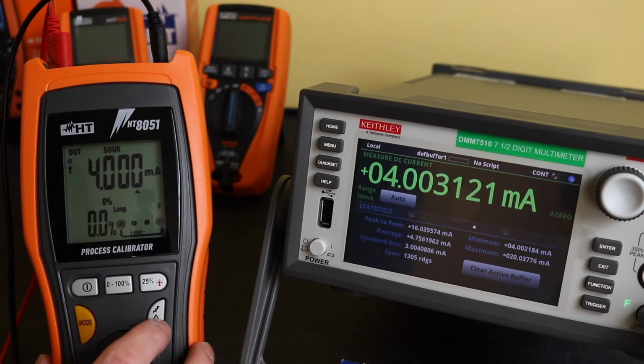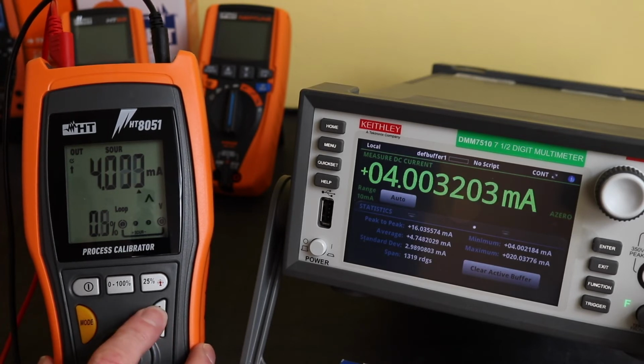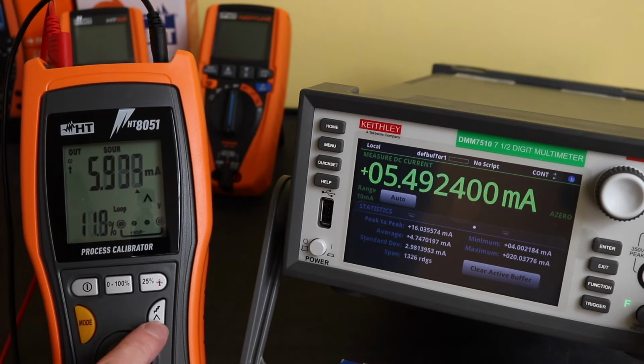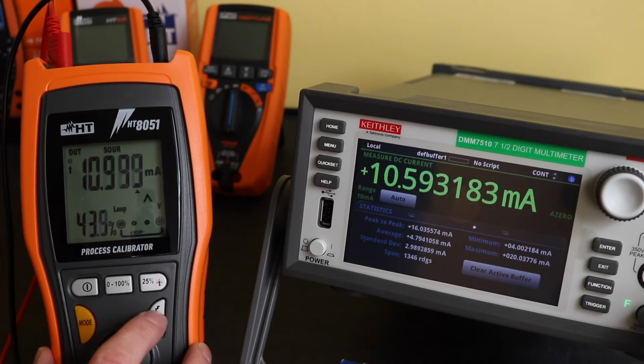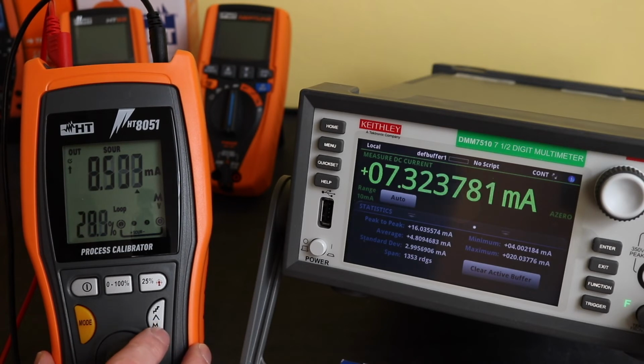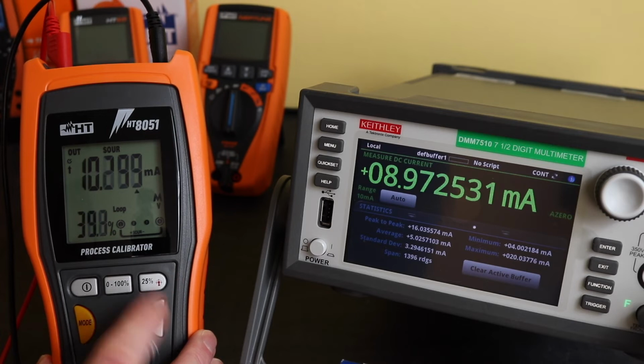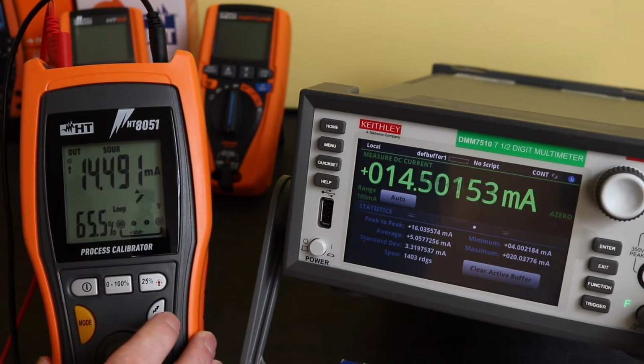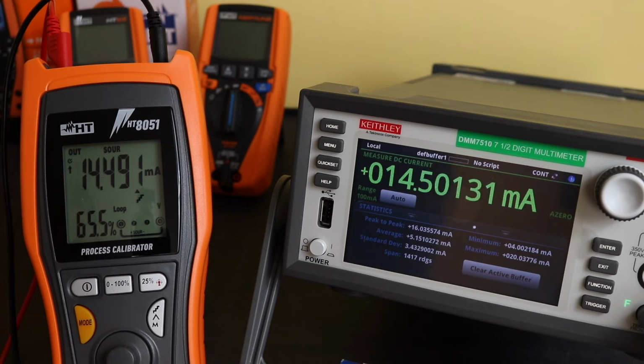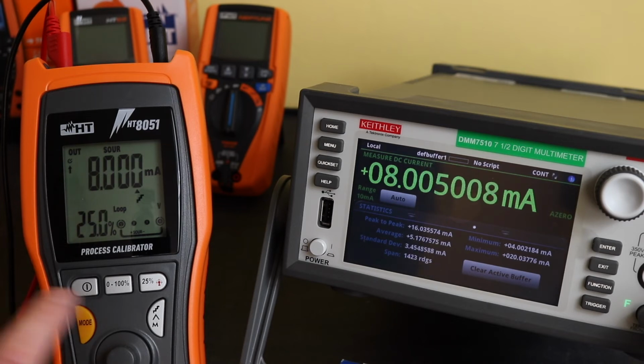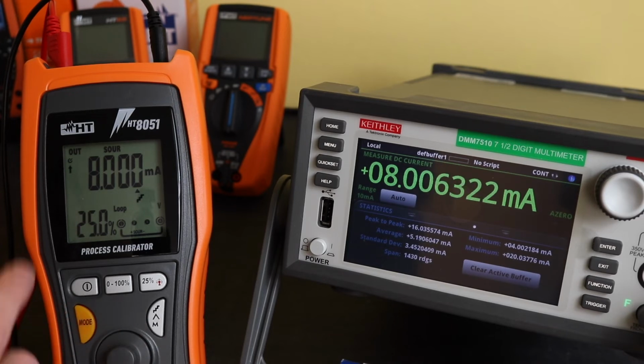The issue that I found with this is it looks like it will go to step ramp first. So when I press this, it's actually gone up to the second one, which is the slow ramp. Press it again, I'm now on the quick ramp, and you can see it really goes up in a 1 micro resolution. It just continually cycles, and then when I press this, you can see it's moved to the 25% step, and unfortunately you have to wait for it to get off that first step, and then it will correct itself and go to a standard 25% step mark.